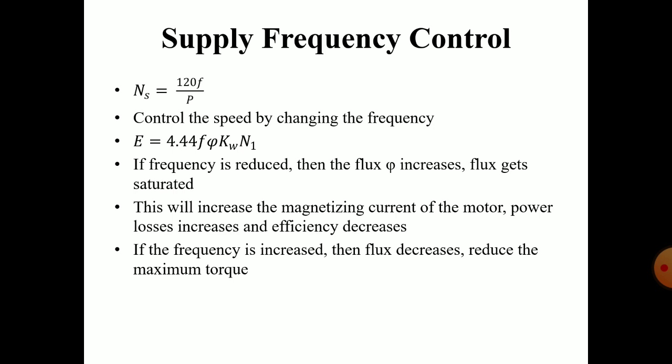So the next method is the supply frequency control method. As I have already told, Ns equals 120 f by P. So by controlling the supply frequency, you can control the synchronous speed of the motor.